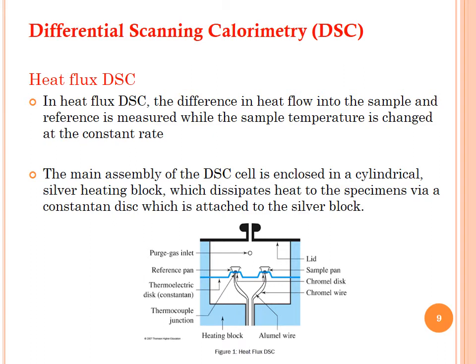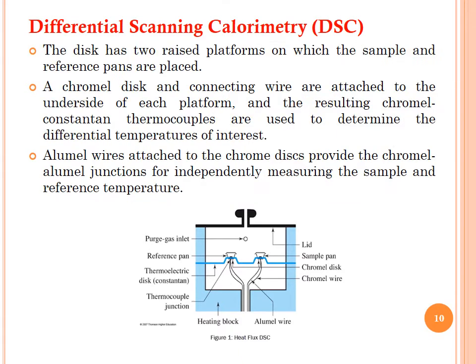In heat flux DSC, the difference in heat flow into the sample and reference is measured while the sample temperature is changed at a constant rate — fixed by the temperature program. The main assembly of the DSC cell is enclosed in a cylindrical silver heating block, which dissipates heat to the constantan disk attached to the silver block. The disk has two raised platforms on which the sample and reference pans are placed. A chromel disk and connecting wire are attached to the underside of each platform, and the resulting chromel-constantan thermocouples are used to determine the differential temperature of interest.